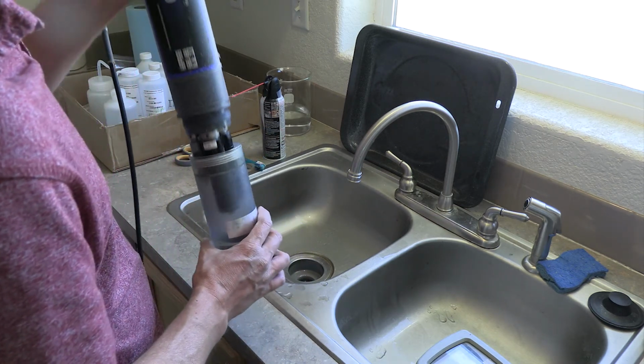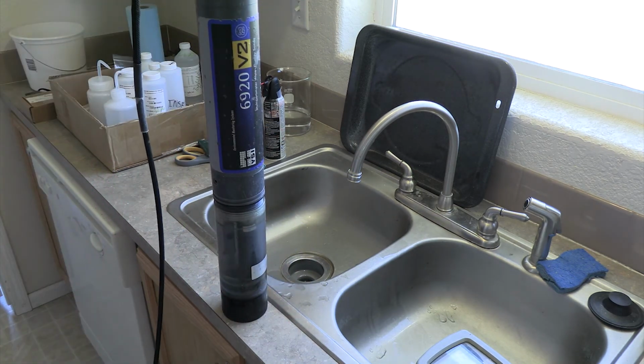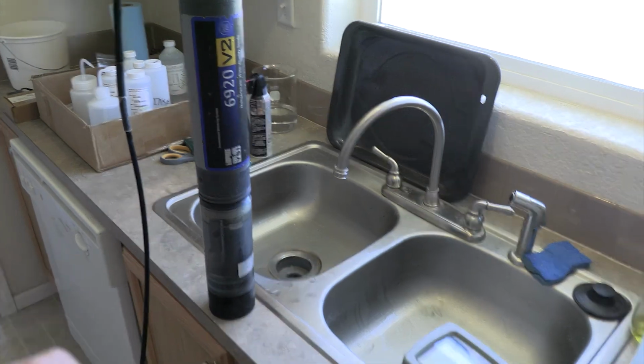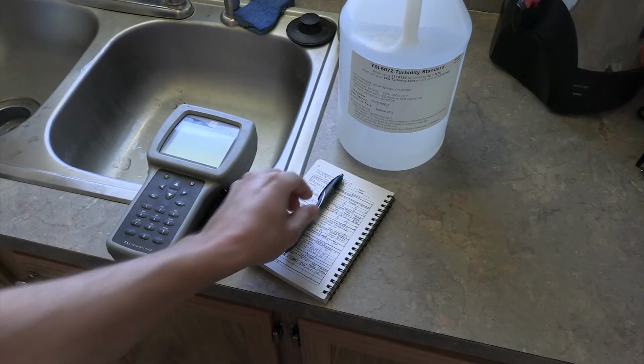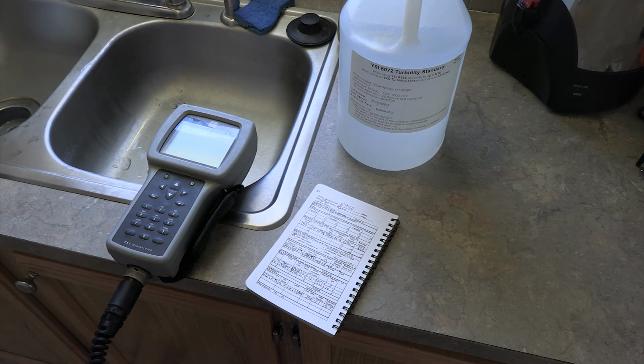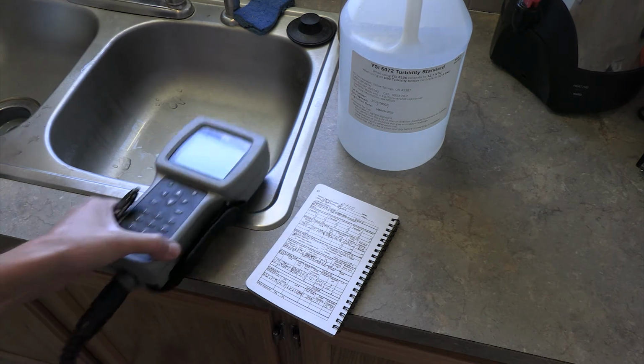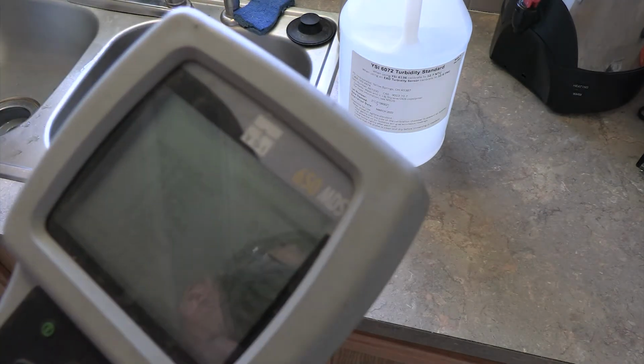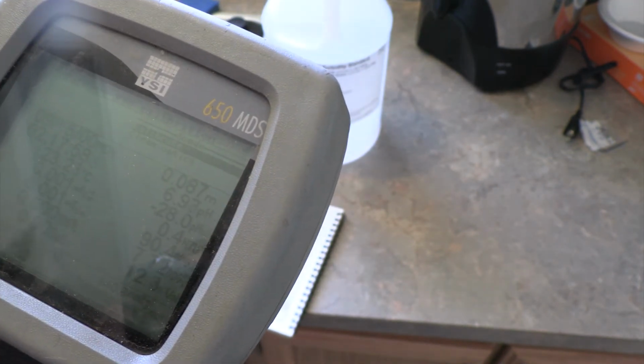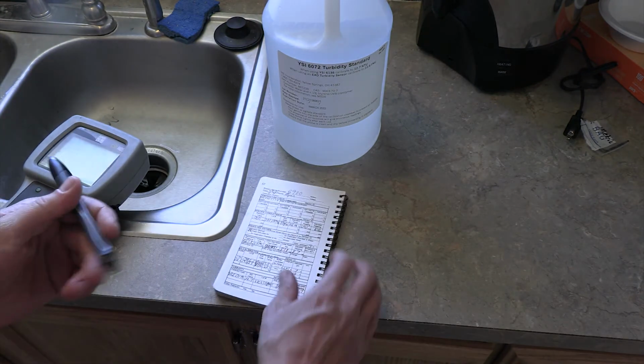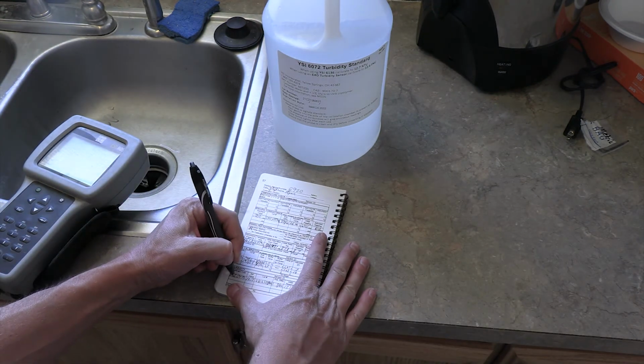Same thing, I'm pretty sure this is one at the bottom, because that's turbidity. So as long as it's over that one of the black probes at the bottom, the turbidity probe should be fine. Alright, so let's go ahead and check out our turbidity. And as you can see, it's about 0.4, which is good, but recommended by YSI, a 0.8 reading would be better, because if it's too close, it will still go negative.